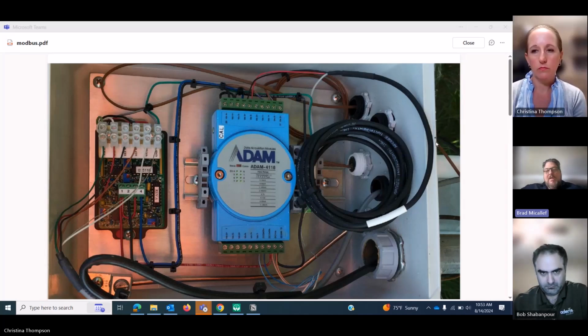So what Wiretap allows us to do is literally tap the transmit and receive wires on the bottom of this ADAM, and then, in running the program, listen for what device IDs are being communicated with, which sensors, and what values are being pulled back in the form of registers. And we can do all that without having to break the current connection and without having to really know anything about how those devices or how the Modbus chain is currently set up.